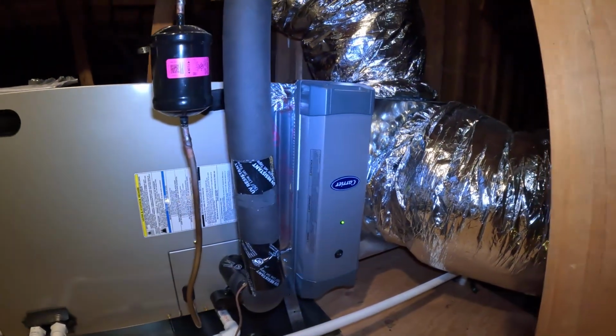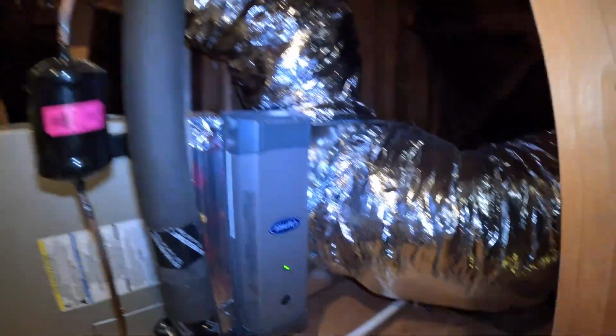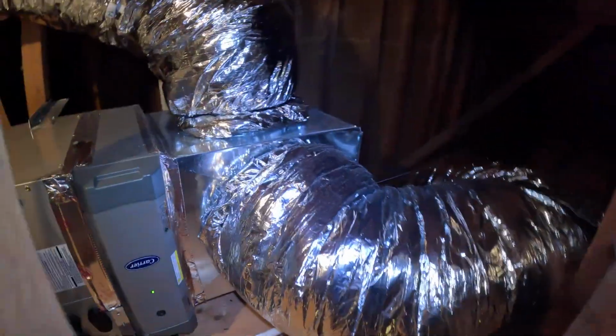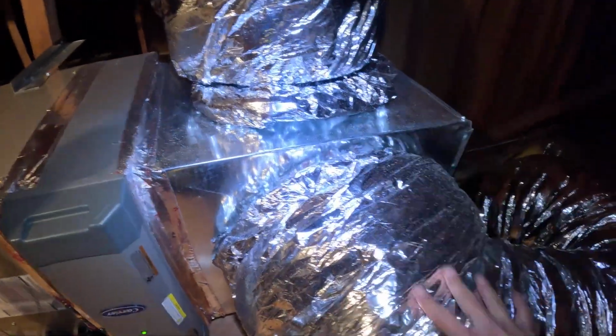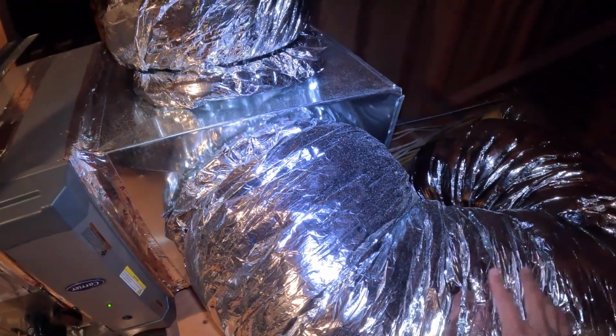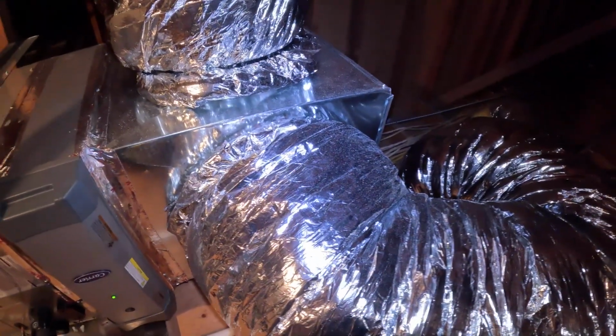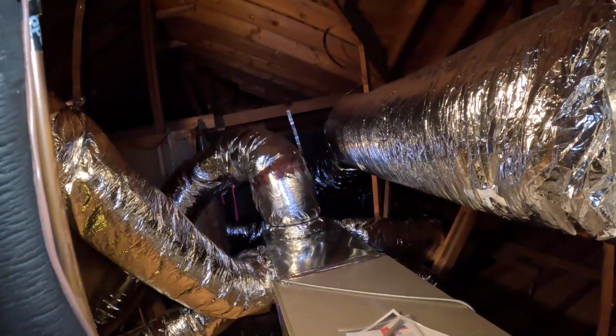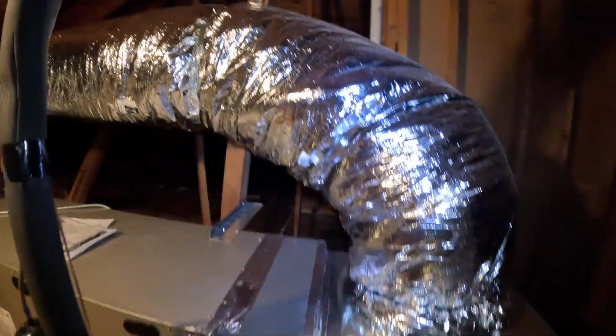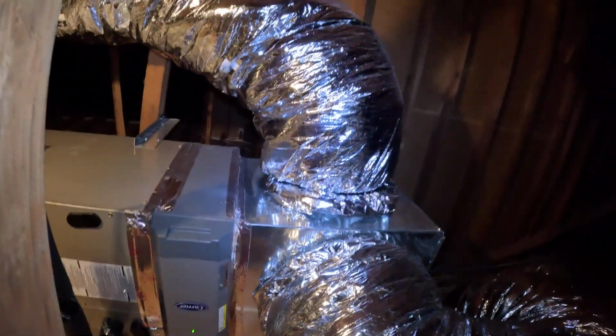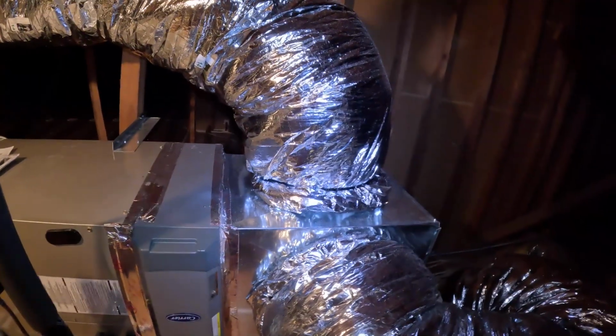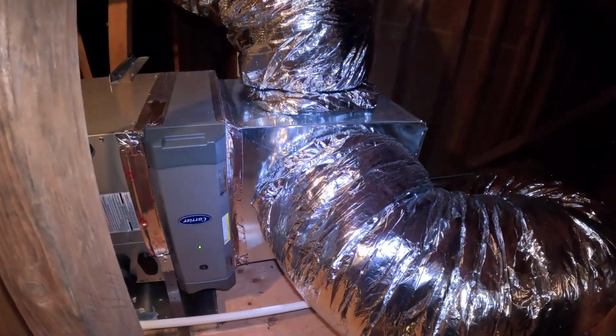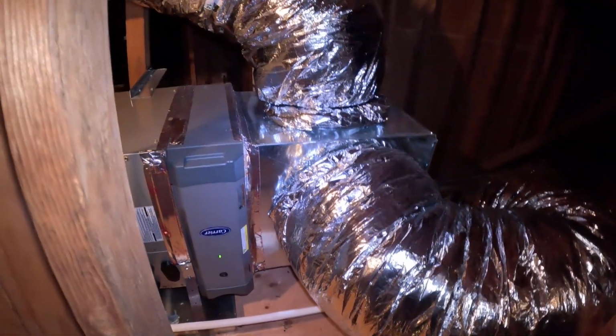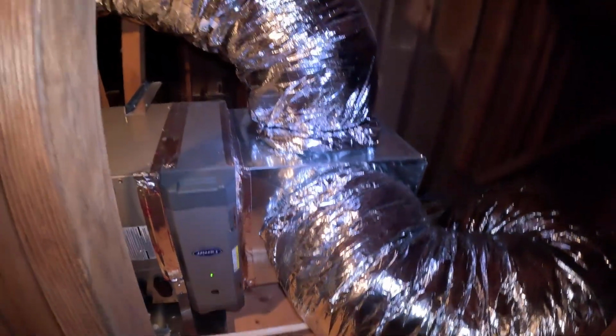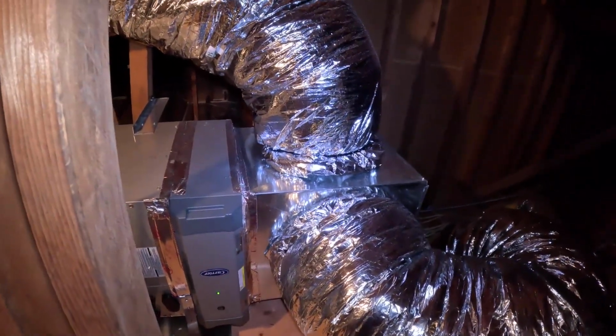It will do a great job of filtering the air. We have our two returns that come off the return plenum right here. This is the biggest return, a 16-inch, pulling about 1,000 CFM of air. Then we have this 14-inch return that runs all the way down and goes to the other side of the house. So it's a very balanced system because we have return air being pulled from two sides. It will cycle the air faster, pull the heat out faster, and be more even throughout the house in terms of temperature. That 14-inch duct pulls about 700 CFM.